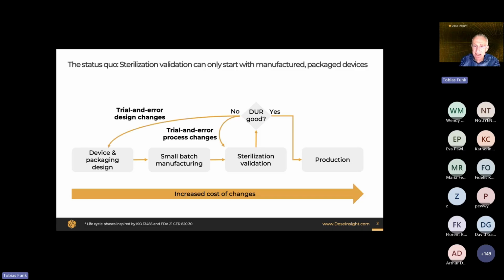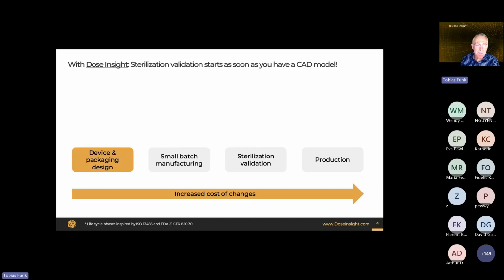However, that does not necessarily happen. There can be outcomes where the dose uniformity ratio is too high. Then you go through a trial and error process to find what the reason is. Hopefully it can be resolved at the contract sterilizer. If not, you basically have to make changes to your design, even packaging, or worst comes to worst, even the device. And then you go back through small batch manufacturing, go through the validation process again, and once you pass it, you go into production. With virtual dose mapping, this process can be condensed and done earlier.